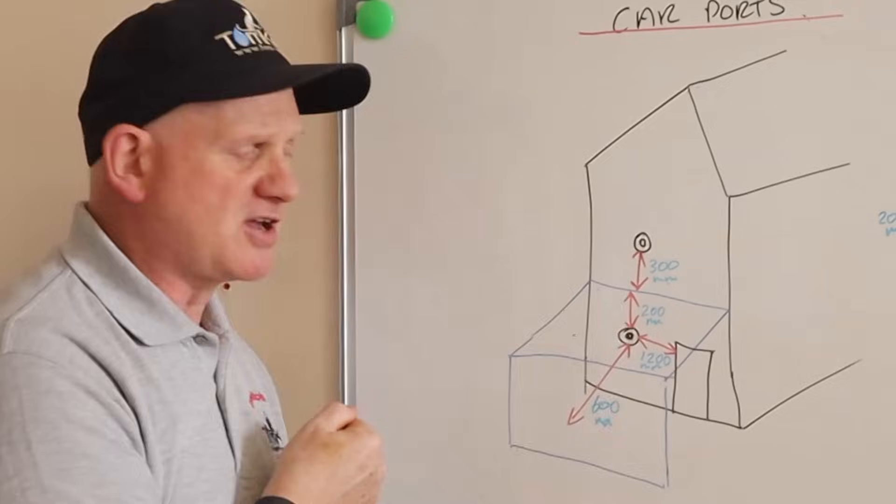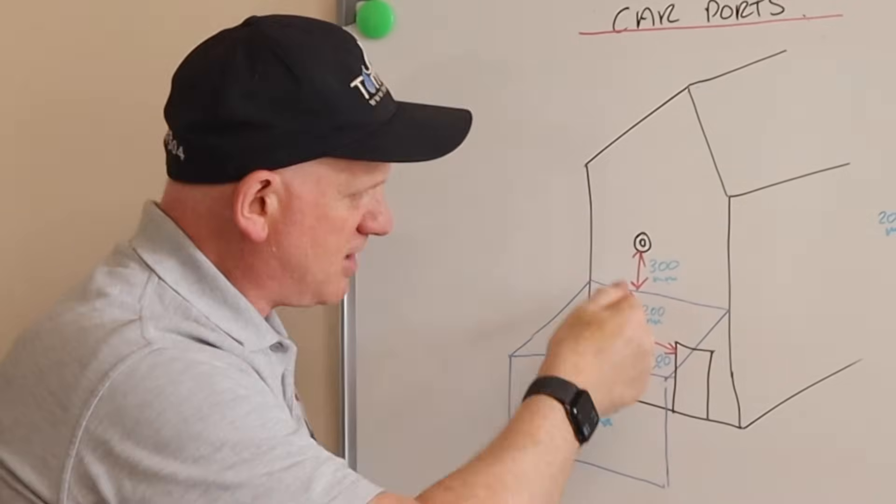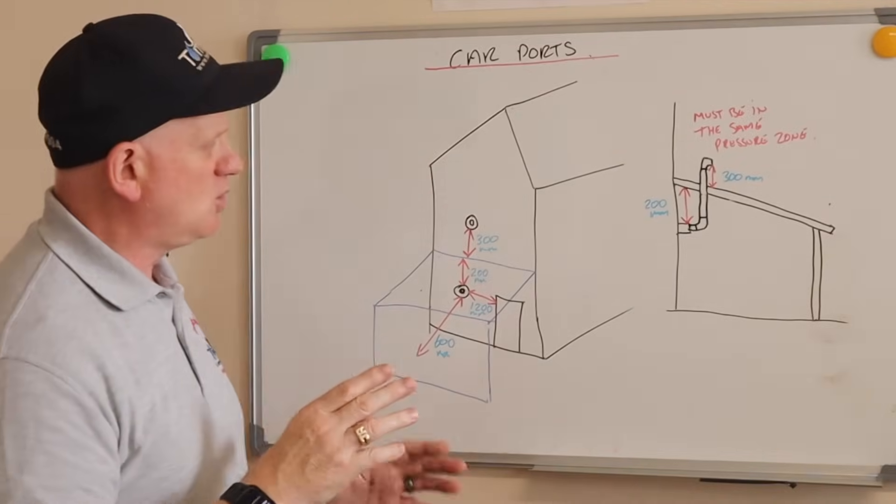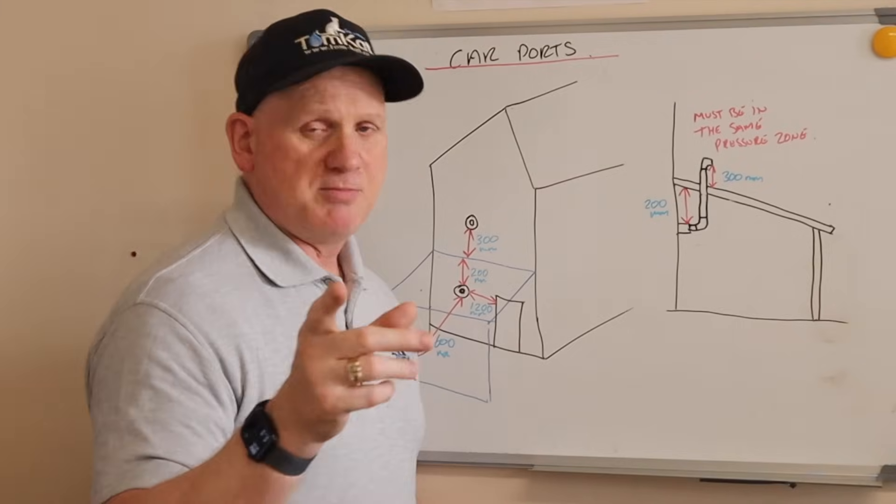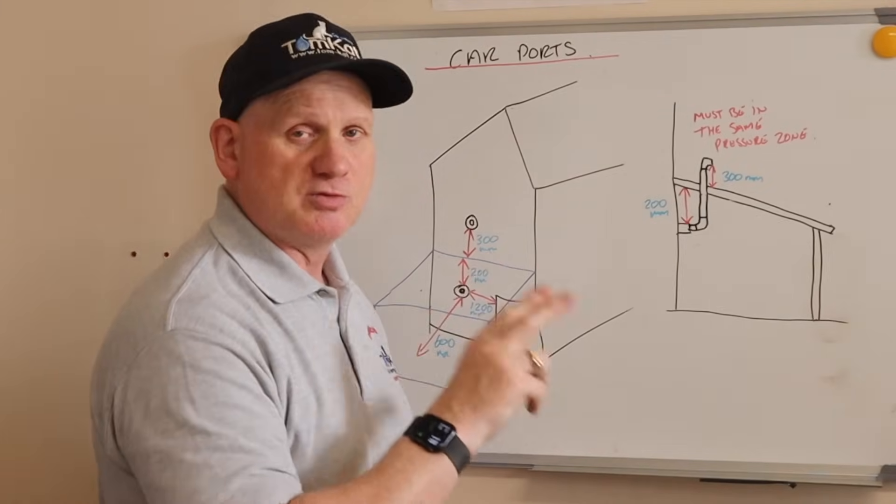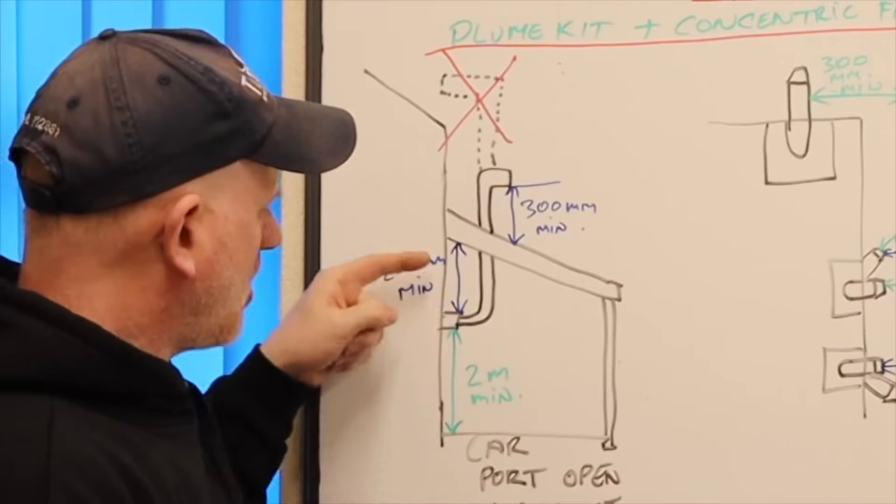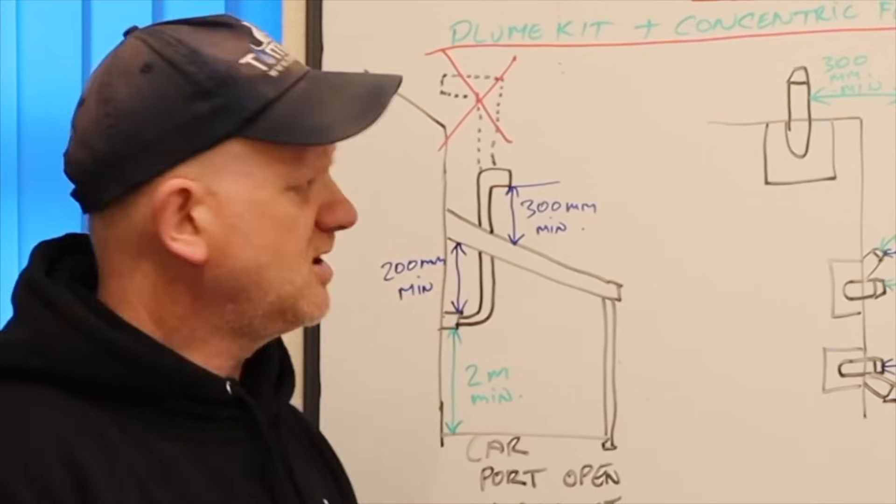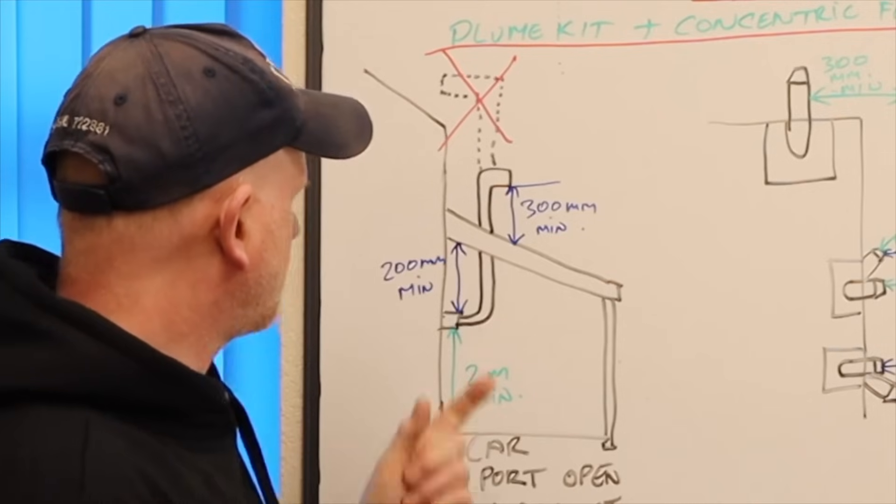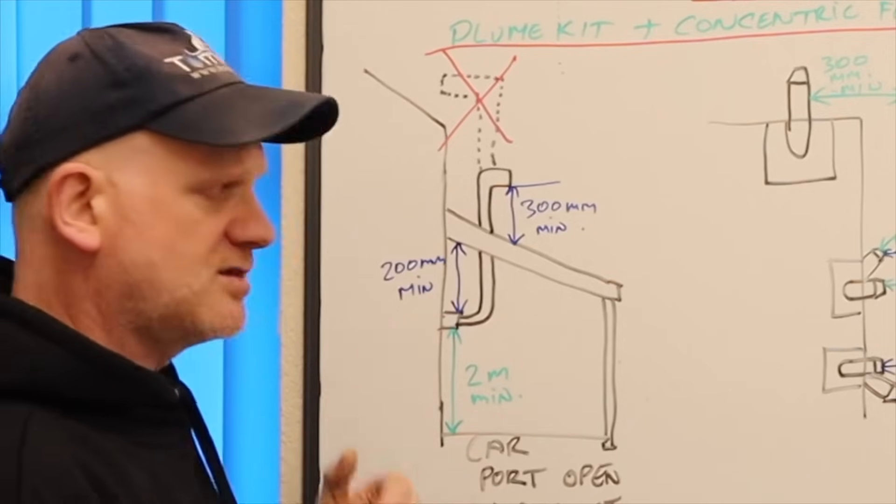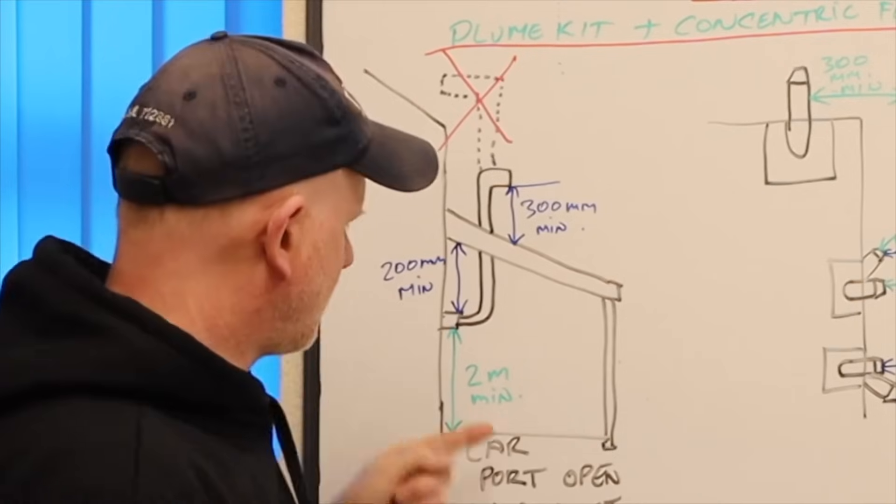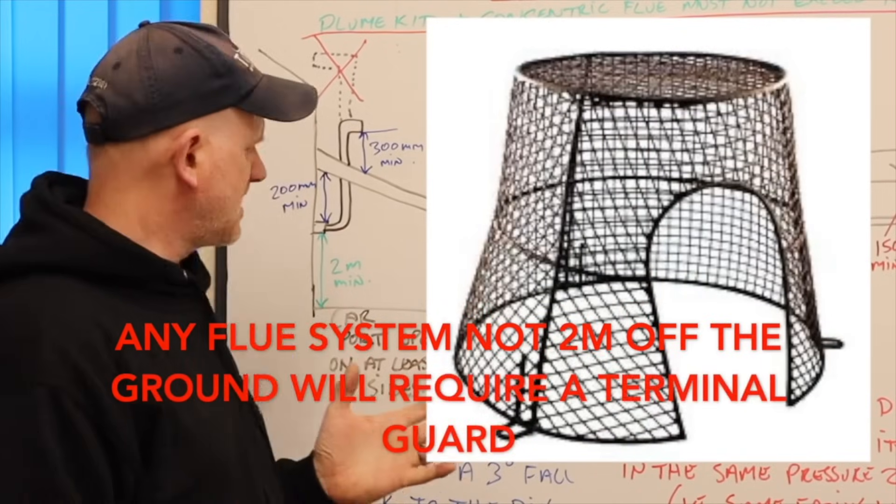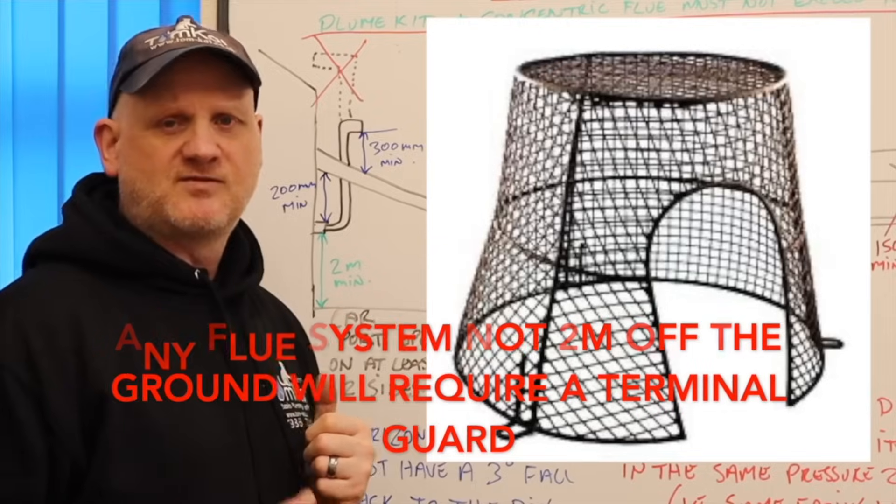And if you add a flue over the top of a carport, we need at least 300mm from the bottom to the top of the roof. So, we can use a plume management kit, remember, if the manufacturer allows you to, to help us with this installation. So, we need to still install the flue as it should be. So, 200mm away from the eaves or the carport. But we still need to be two metres off the floor.